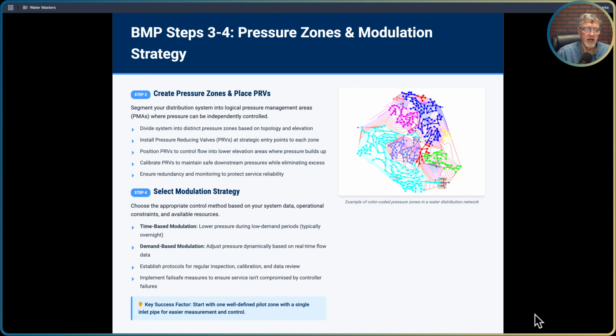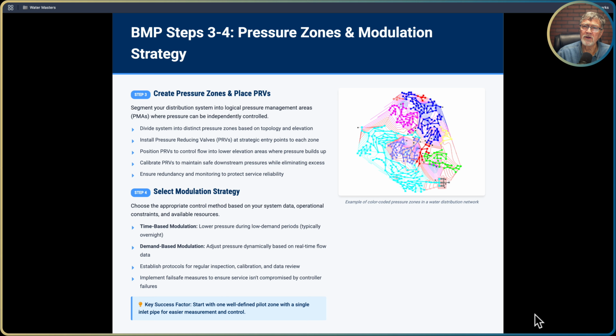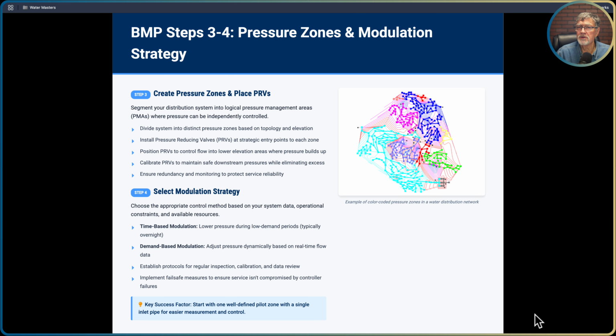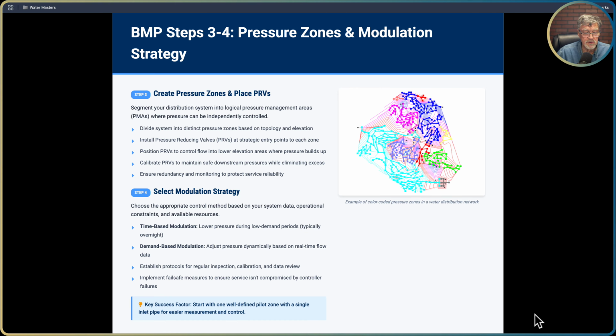Getting a little more complex, we have demand-based modulation. You're adjusting pressure dynamically based on real-time flow data. You're going to have flow meters that are tied into your PRVs, and you're going to adjust the pressure in your pressure zones using the flow data. That's happening continuously as the flow data is fed into the PRVs to maintain the same water pressure. We want to establish protocols for regular inspection, calibration, data review, and implement fail-safe measures to ensure service isn't compromised by controller failure. So always have some backups.